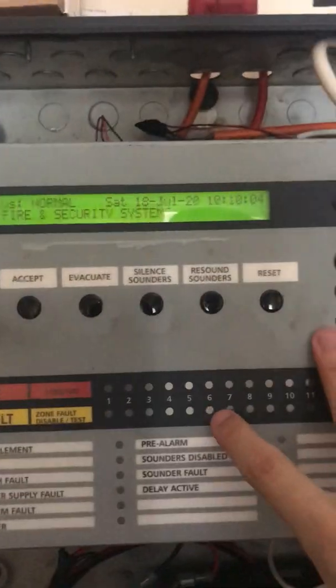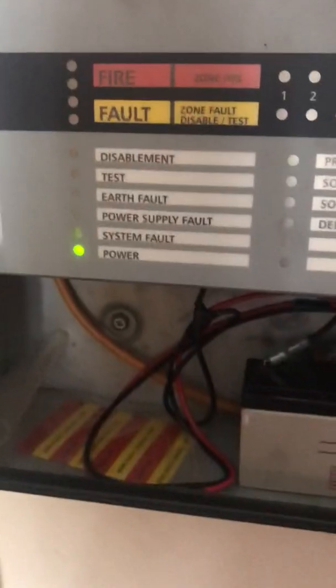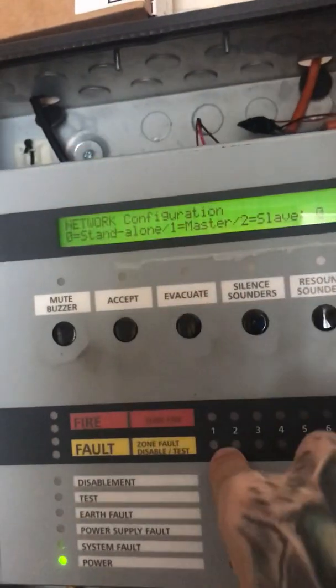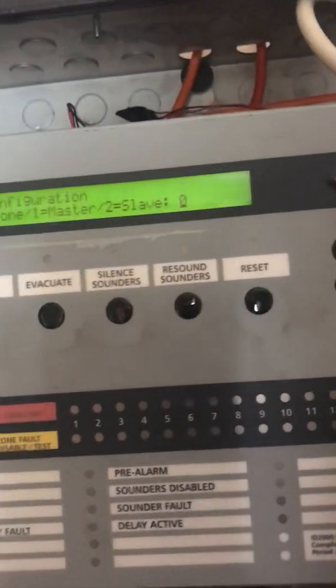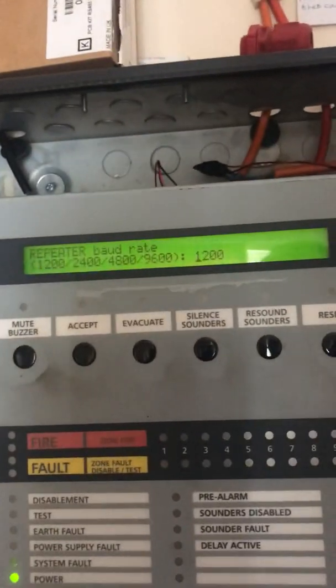That goes straight into the repeater panel. So, how to set up a repeater? You go into the configuration, put the passcode in. You need the backdoor code for this. Now we're in as the engineer. Press 9 for network configuration. Clear corrupt data counter? Nope. For repeater, we choose standalone. Number repeater is 1. Repeater comms fault treatment — you need to enable that. Repeater baud rate, that's perfectly fine: 1200. The system has now got a repeater panel.